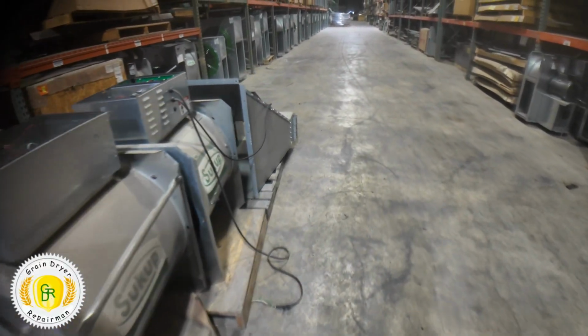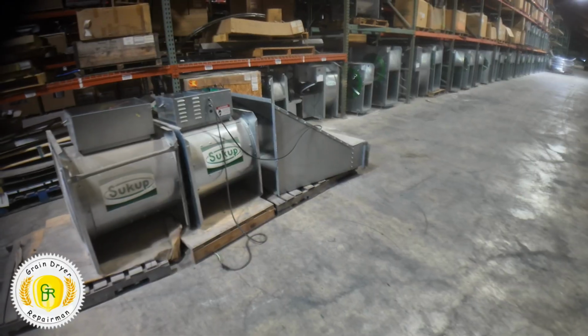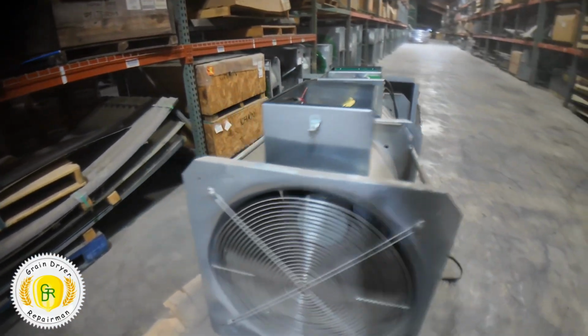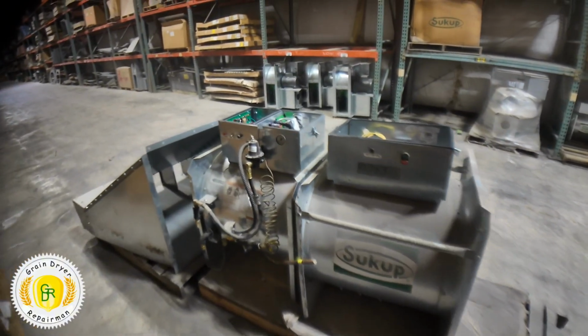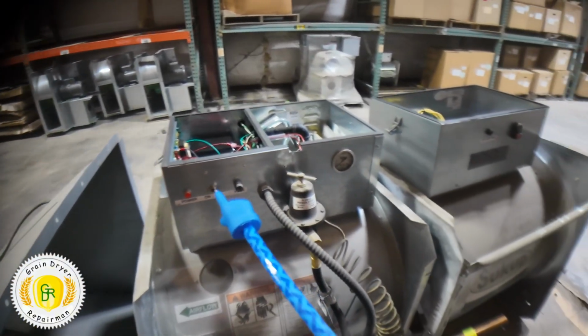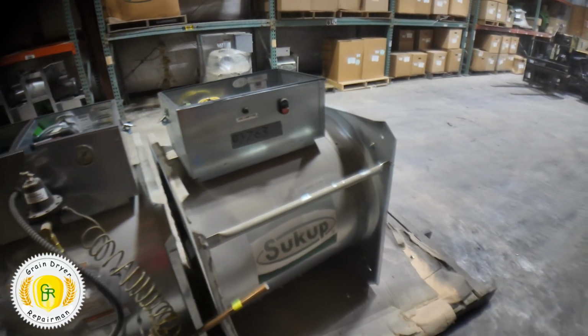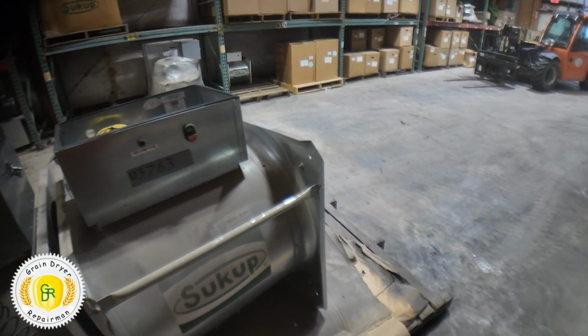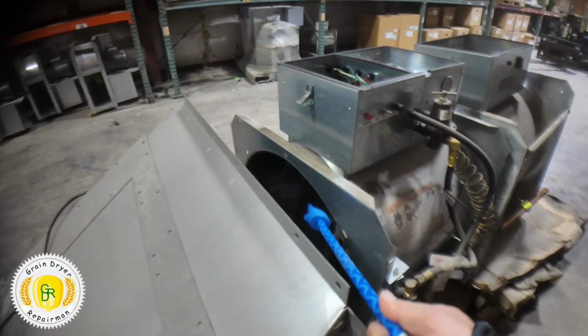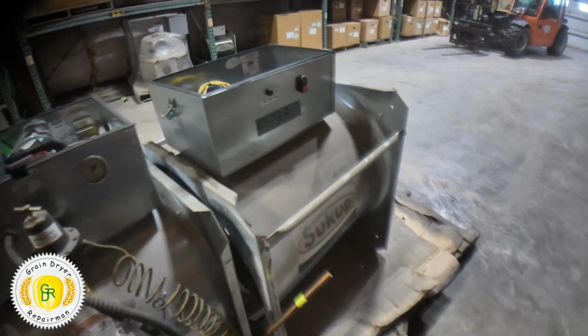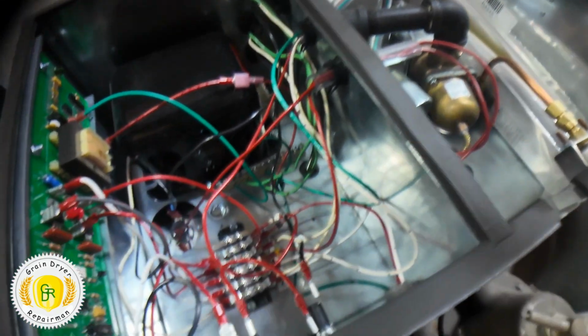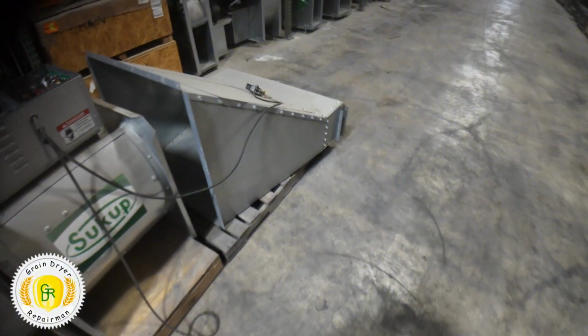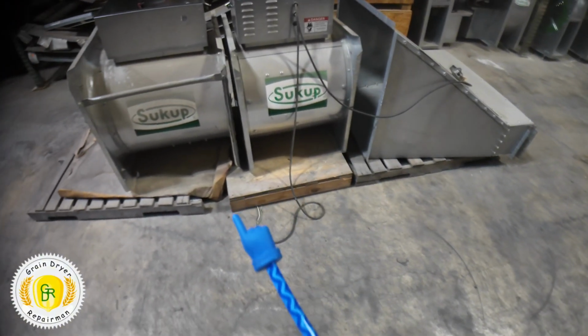One time I got to a grain bin where there was a fan and heater mounted on a grain bin. And when the customer turned on the toggle switch, the burner lit without the fan running. What happens then is all of the wires inside get burnt, and the housing high limit trips. That's because all the safeties, other than the primary safety, were not all in place yet. I would like it if all of these were installed correctly.